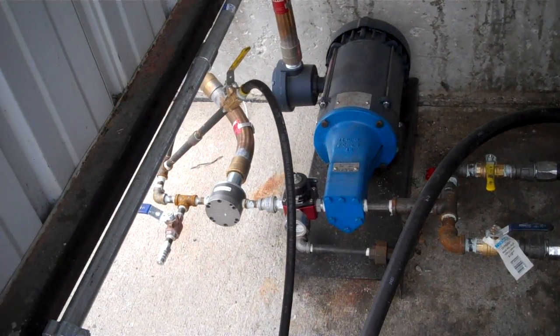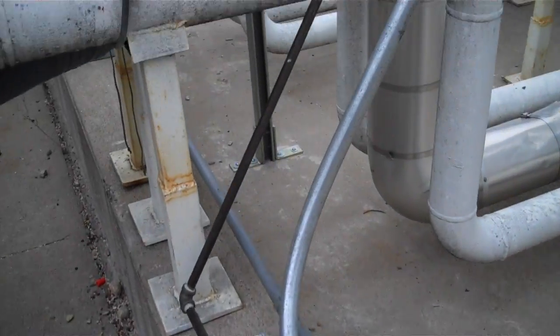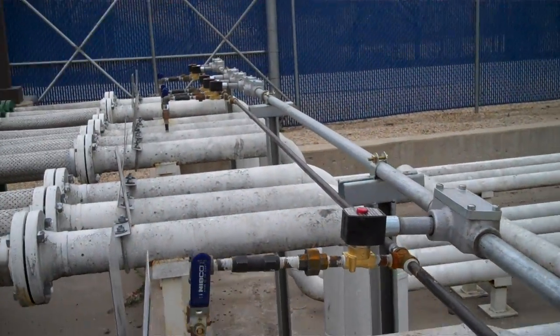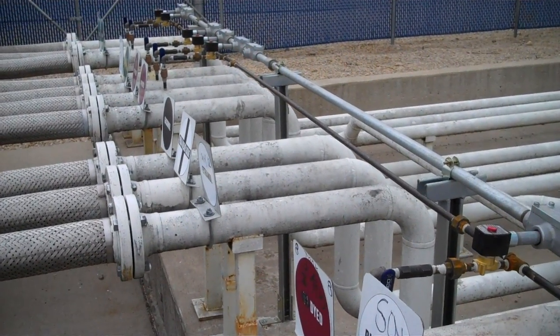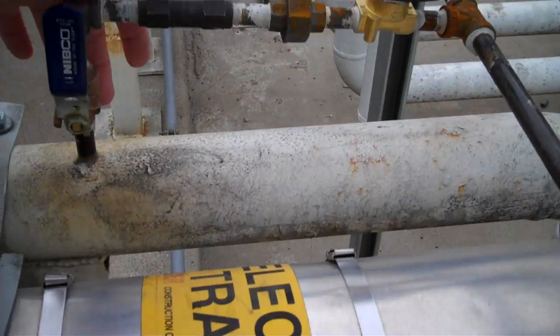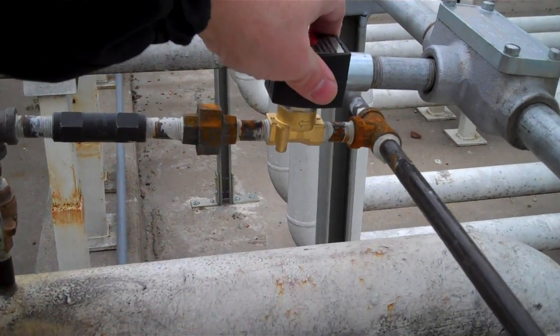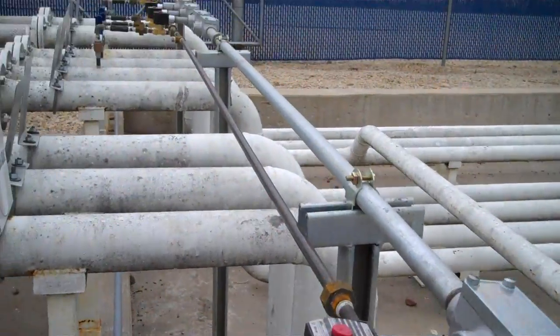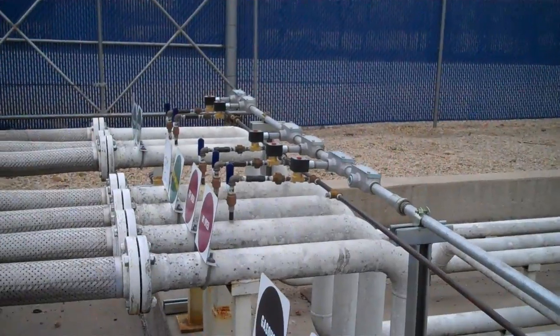I'll show you from the pump going through the meter. We have a calibration port down there. Coming around and following the piping, it goes out to all the transport lines. At each transport line where they want to add additive, they've got an injection point — drilled and tapped quarter inch — with a ball valve, a check valve, and a solenoid valve.